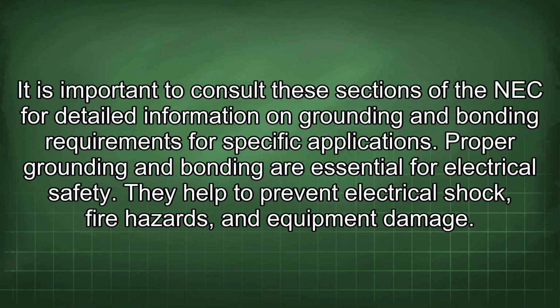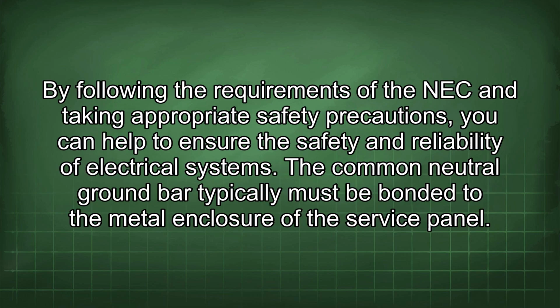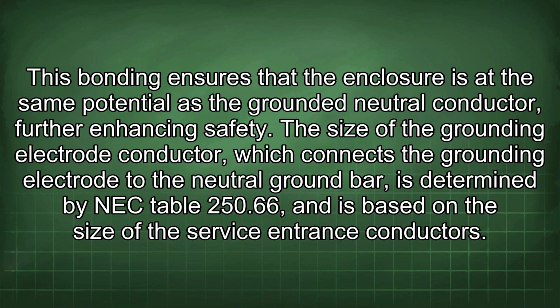Proper grounding and bonding are essential for electrical safety. They help to prevent electrical shock, fire hazards, and equipment damage. By following the requirements of the NEC and taking appropriate safety precautions, you can help to ensure the safety and reliability of electrical systems. The common neutral ground bar typically must be bonded to the metal enclosure of the service panel. This bonding ensures that the enclosure is at the same potential as the grounded neutral conductor, further enhancing safety.